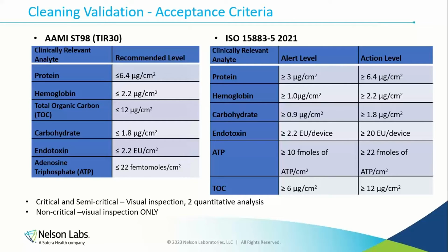So if you are submitting to the EU, you probably want to also assess the ISO 15883-5 standard in your design history file, and write a paragraph on how it's still relevant. Those are things you probably want to consider.